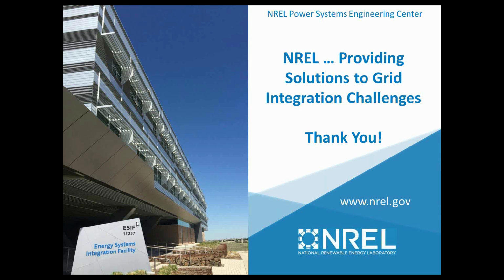I think at the end of the day, if you look at how unintentional islanding is set up in the document, it's kind of like a catch-all, the last resort to make sure that you're not creating an island. But you still would need to be coordinated, and you still need to be tripping outside or inside the trip points as listed in the document. It may be one of the things that 1547 evaluates: do you really even need an unintentional islanding requirement if all your other things, like recloser coordination and voltage and frequency trip points, are needed? I'll just throw it out there for discussion.